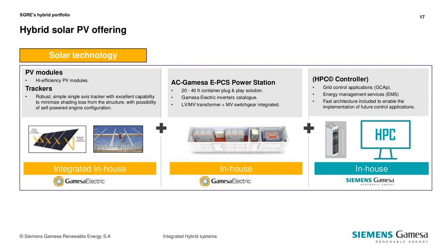In our solar offering, you have the DC, AC, and controls. The DC system being the panels - today SGRE does not manufacture panels, but we can integrate, purchase, and rack any of the large panel manufacturers. This is coupled with our AC system, which is our proprietary inverter system, within a 20 or 40-foot container, about 2.5, and now we've just released our 3.7 MVA inverter, all UL certified 1500, within a containerized solution with the switchgear and transformer. Finally, the HPC, which is integrated for solar plus - solar plus wind, solar plus battery, etc.